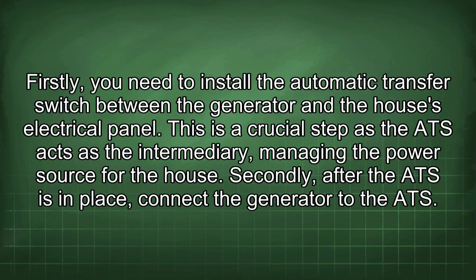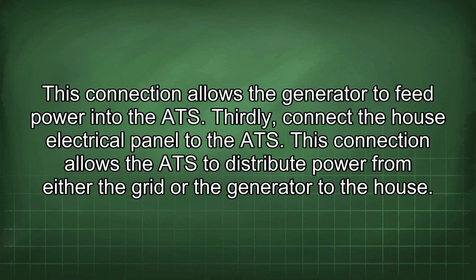Firstly, you need to install the automatic transfer switch between the generator and the house's electrical panel. This is a crucial step as the ATS acts as the intermediary, managing the power source for the house. Secondly, after the ATS is in place, connect the generator to the ATS. This connection allows the generator to feed power into the ATS.